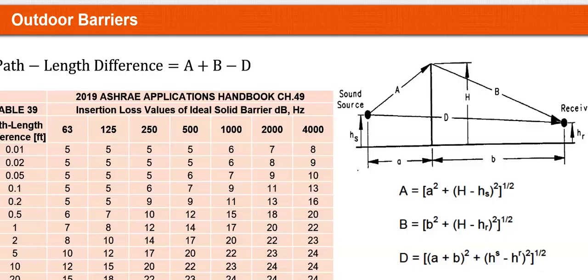But if sound waves did not bend, which they do, barrier walls would be the ideal isolators. But because of diffraction, those waves bending over, you have to really pay attention to the distance to the receiver and have parameters to size the right height of your barrier wall. So some of the sound is going to be what gets transmitted through, and some of it is going to be what goes over and down to the receiver. So that is typically governed by doing a path length difference equation. So the longer the path length, the more attenuation you're going to have.